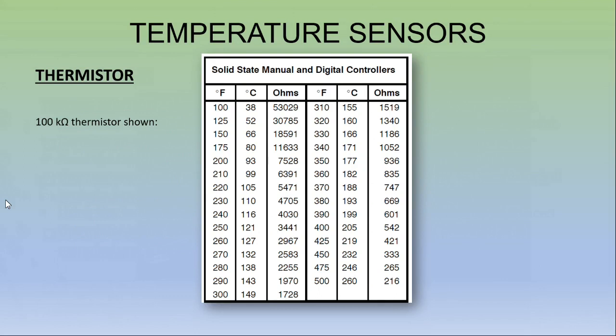It's called a 100 kilo ohm thermistor, and it does not show the nominal rating of 77 degrees. If it did in Fahrenheit, then we would be seeing resistance of 100 kilo ohms. This one here actually happens to be for an oven, so it takes big jumps. You notice that from 100 degrees Fahrenheit, it still has 53,000 ohms. But then you go to 200 degrees, it's dropped all the way down to 7,500 ohms. And you go to 300 degrees, it's down to 1,728 ohms. So a huge drop in resistance per degree of temperature change.